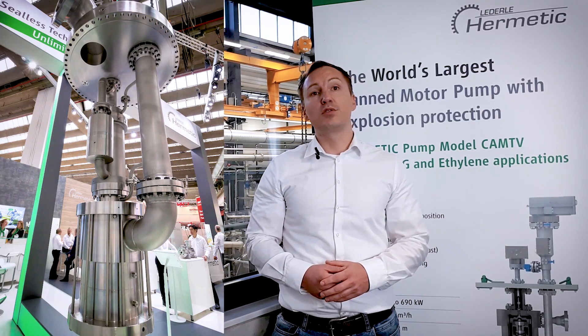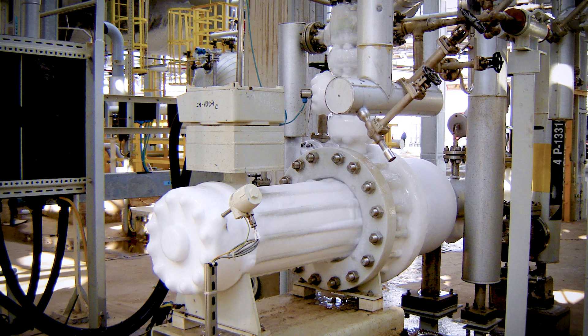As an example, on the next picture, you see a pump that is used in a gas processing plant for nitrogen and methane. It is driven with 176 kilowatts at a temperature of minus 120 degrees, with an operating point of 190 meters head and a capacity of 900 cubic meters per hour. Our pumps are often used in applications with high pressure circulation of gases or supercritical chemicals, and we deliver a pressure range up to 1200 bars.